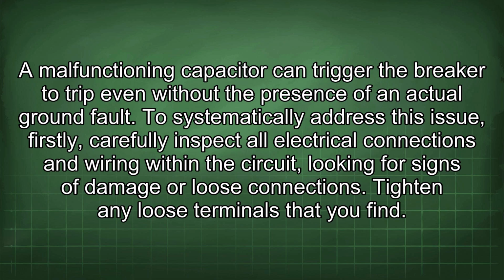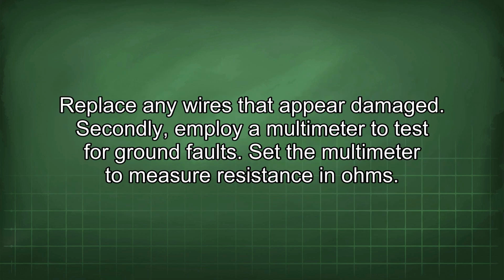To systematically address this issue, firstly, carefully inspect all electrical connections and wiring within the circuit, looking for signs of damage or loose connections. Tighten any loose terminals that you find. Replace any wires that appear damaged.